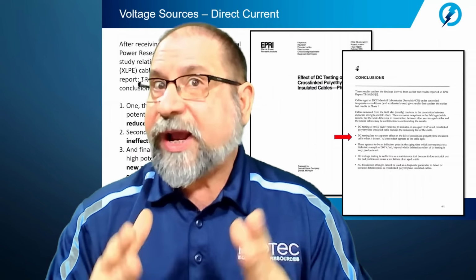All right, let's now talk a little bit about when is it acceptable to use high potential DC. Again, our choice would normally always be to test at power frequency AC, but because of the potentially large and expensive test equipment, DC can be viewed as an option for high potential testing. But when is it appropriate to use DC? We already learned when it comes to medium voltage power cables, service-aged extruded dielectrics, probably not a good idea to use high potential DC. So let's take a deeper look into this. When is it okay to use DC?